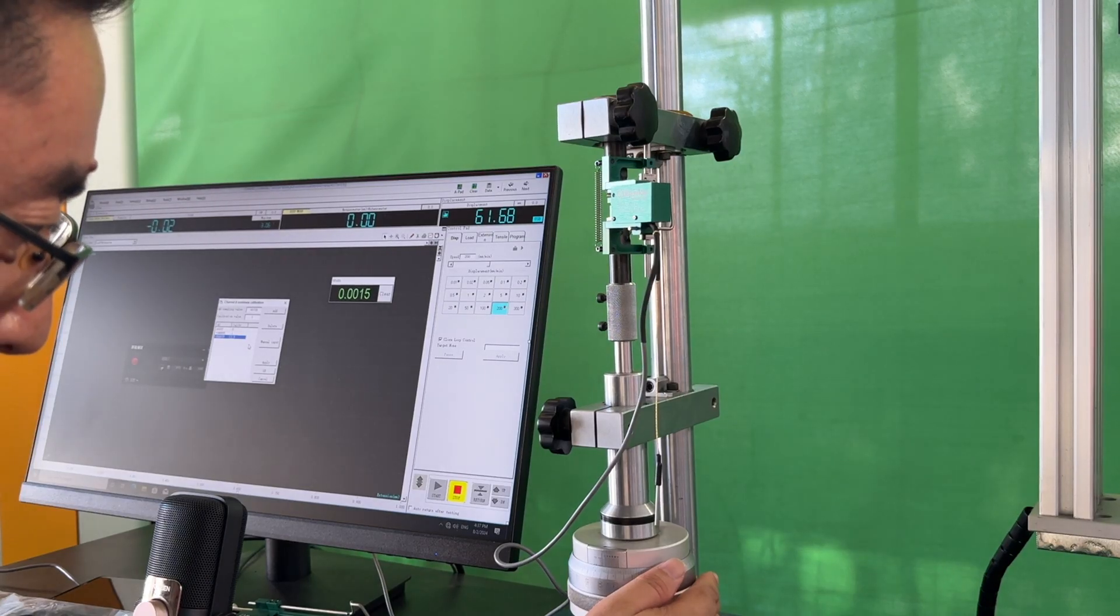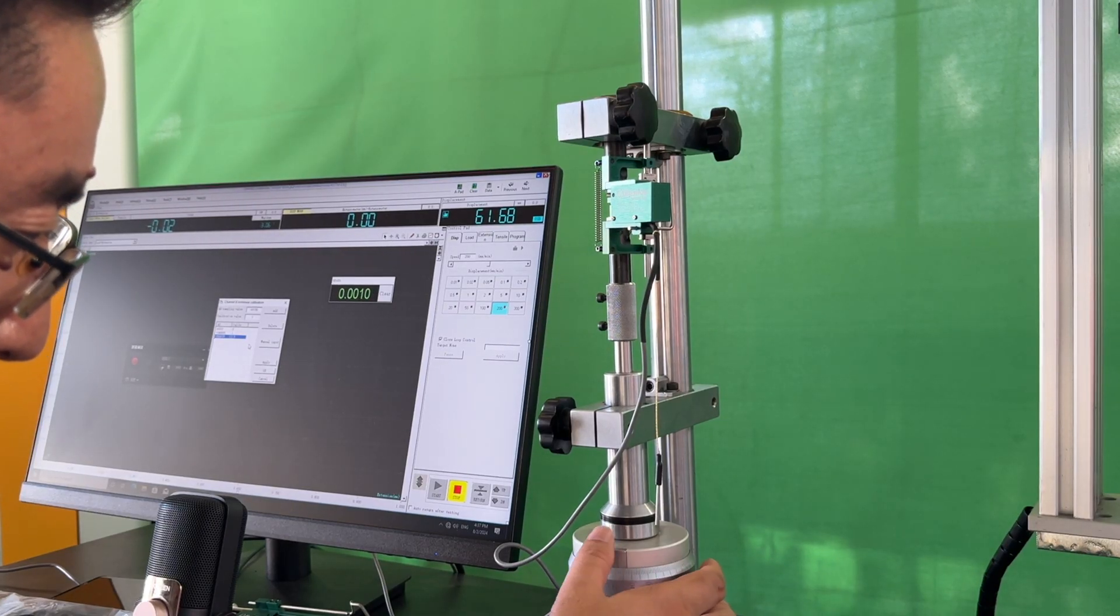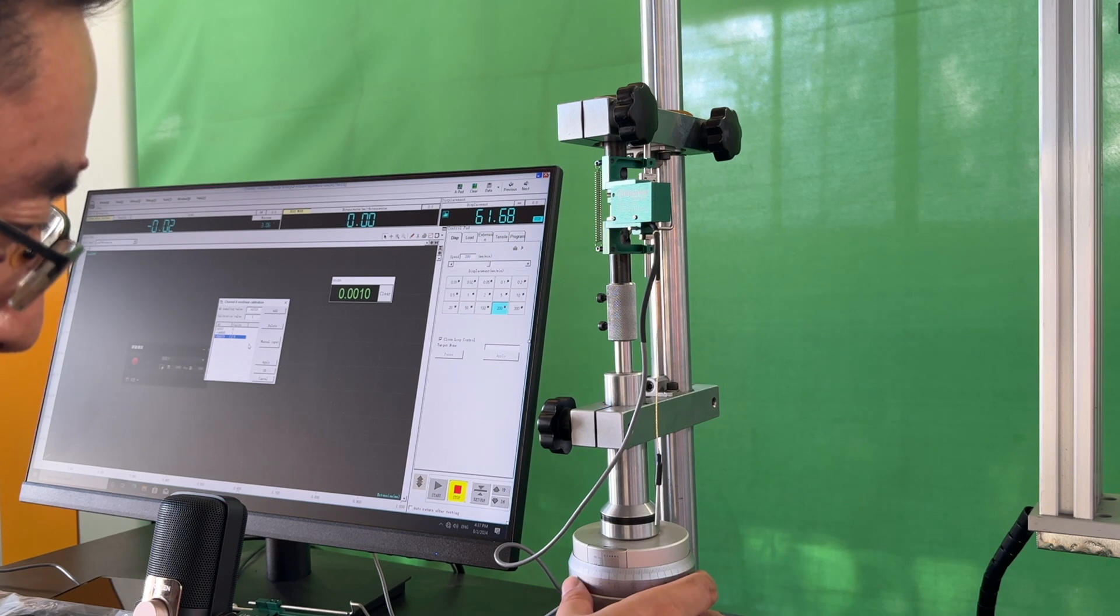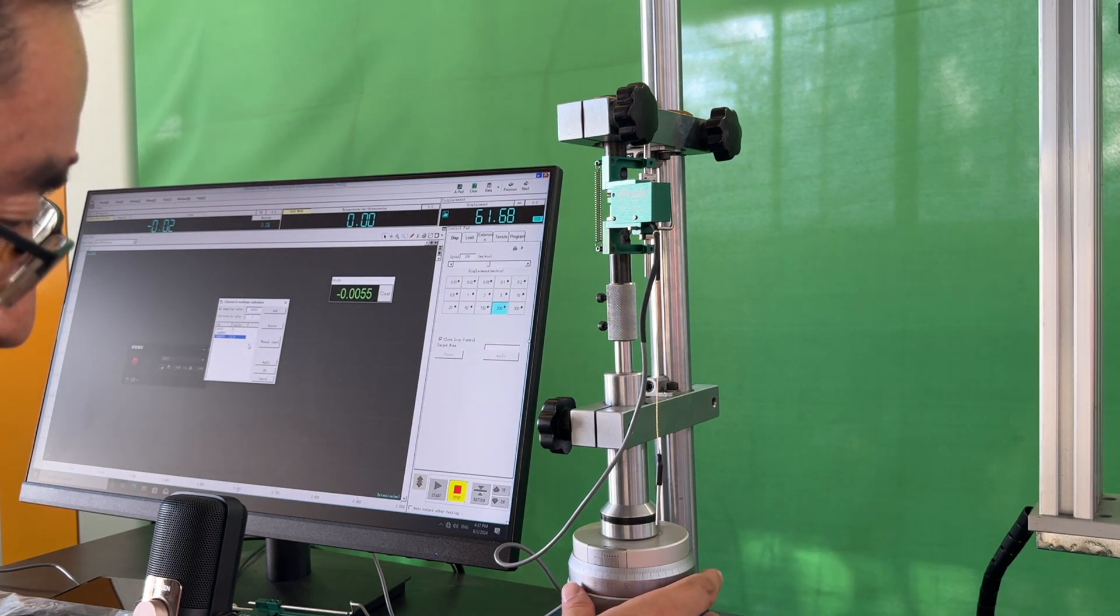Input 0 in the calibration value field and click Add. For the first point, we will calibrate at 1 millimeter. Now that it is at 1 millimeter, click Add and we will move to the next point, 2.5 millimeters. Add 2.5 millimeters, click Add, then click Apply and finally click OK.